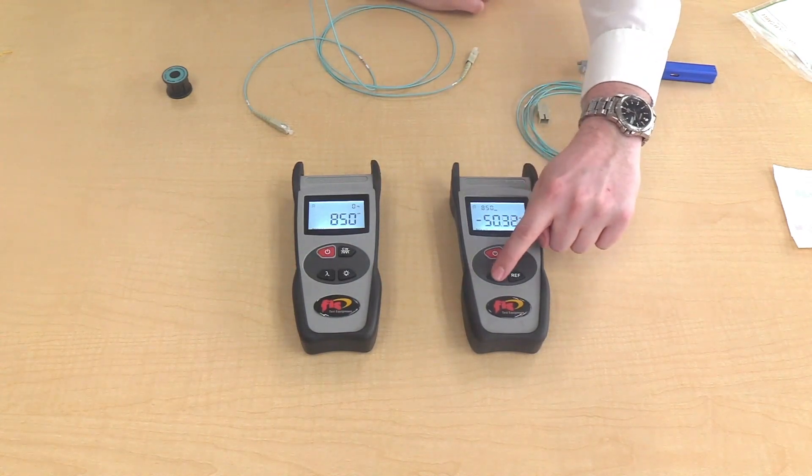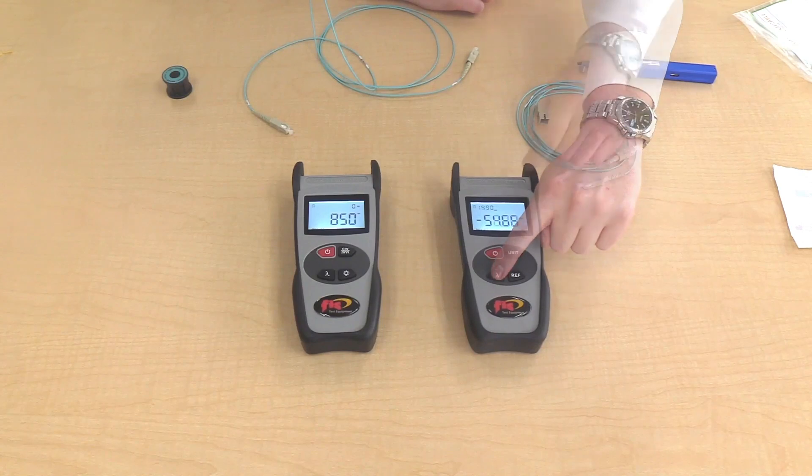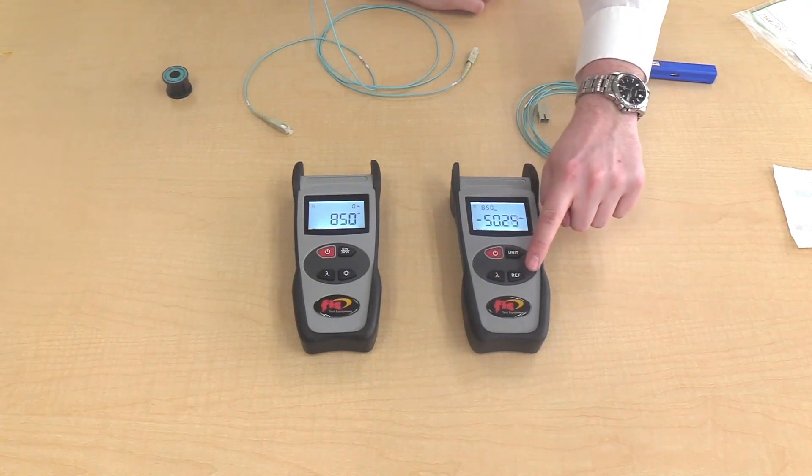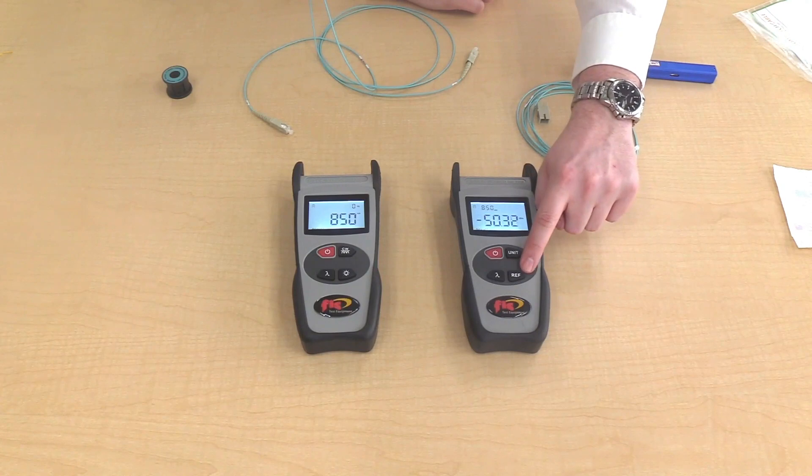To change the wavelength, press the lambda symbol. The bottom right button is the reference button. This is for it to measure relative loss on patch cord or cable.